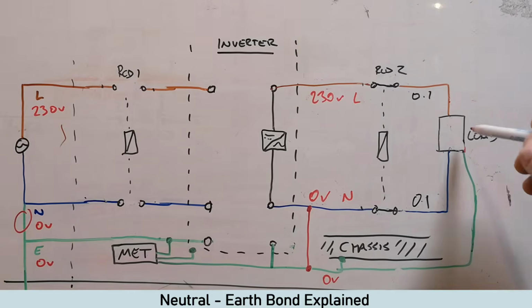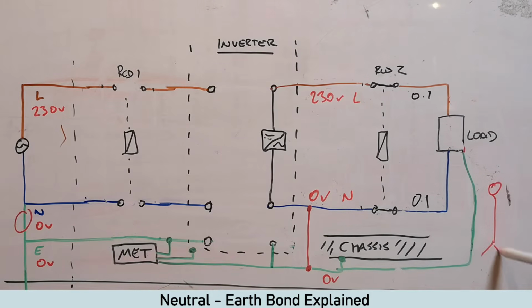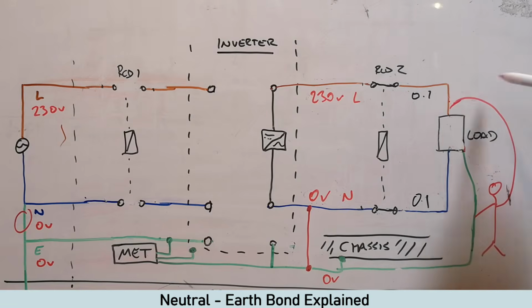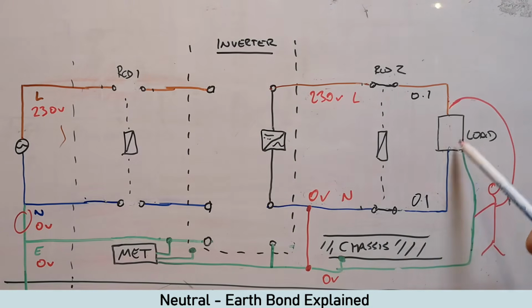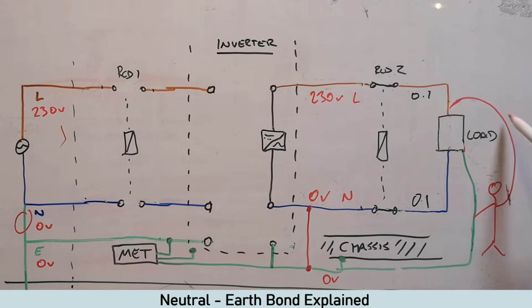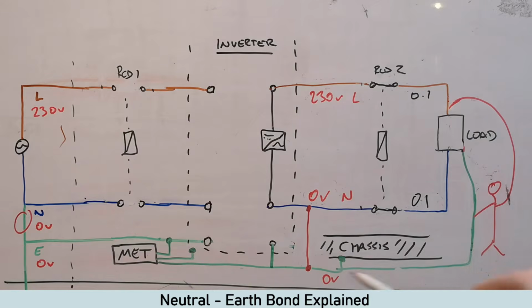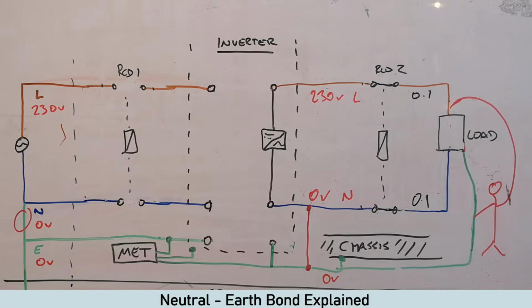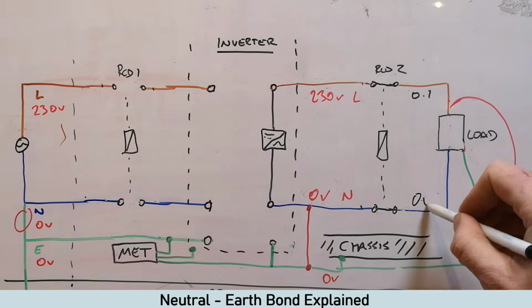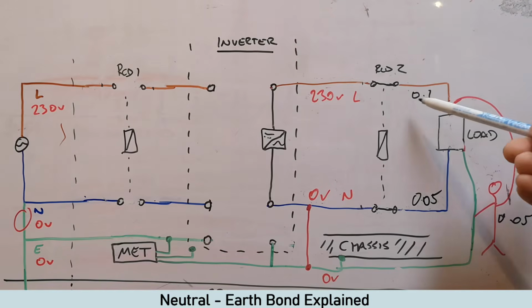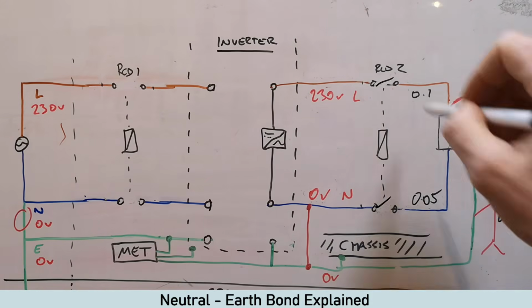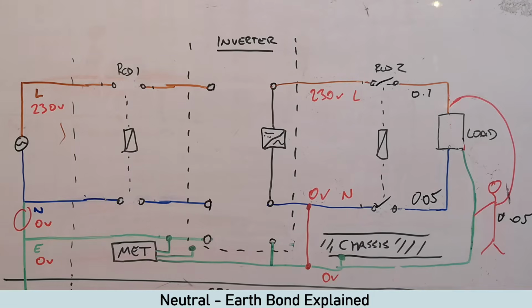So if we introduce you again, let's put you in, it's just a bit better. So you're touching the earth, you're touching that live. So the live's going to come through into the load and back through the neutral, fine, but some of it is down you to the earth again. If you follow that earth, there's now a link here, so it brings it back into the inverter. So it's actually flowing round that way. So that again is going to create an imbalance. Let's do 0.05 again, just to make it easy. Obviously 0.05 is different to 0.01, so it's going to disconnect. Click, and turn you off, so you're not going to be zapped.